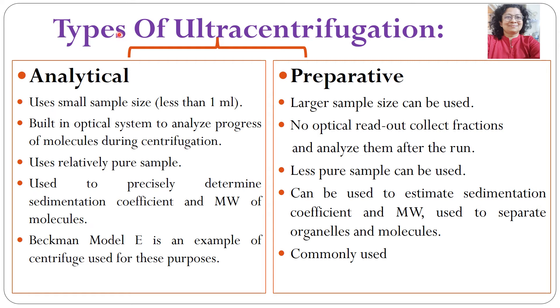Comparing analytical and preparative ultracentrifuge: analytical centrifuge uses a very small sample size of less than 1 ml, while preparative centrifuge can use large sample volumes. Analytical centrifuge is built on an optical system to analyze the progress of molecules during centrifugation, uses relatively pure samples, and is used to precisely determine the sedimentation coefficient and molecular weight. Preparative centrifuge uses less pure samples, can estimate sedimentation coefficient and molecular weight, and is used to separate organelles and molecules. An example of analytical centrifuge is the Beckman Model E.